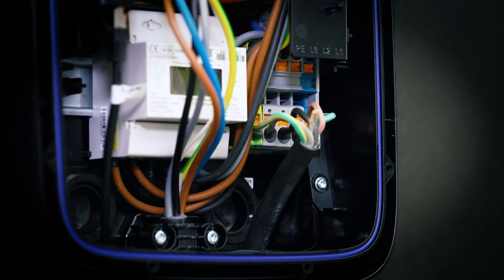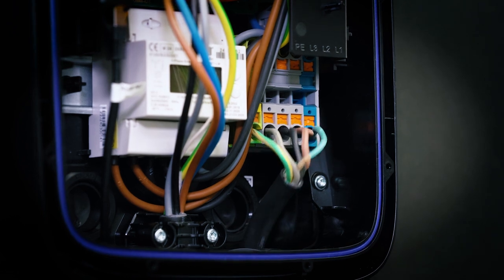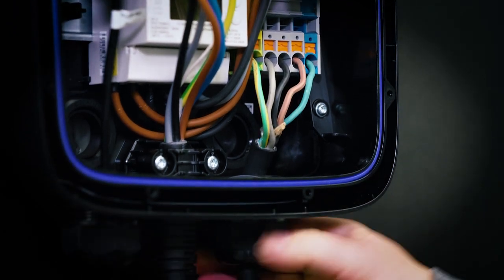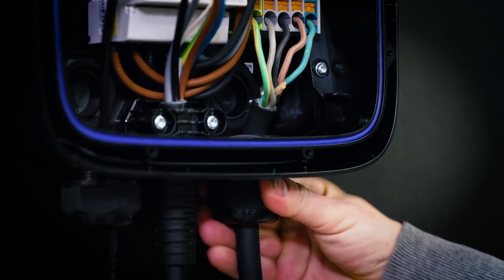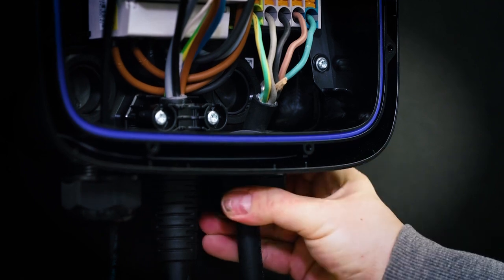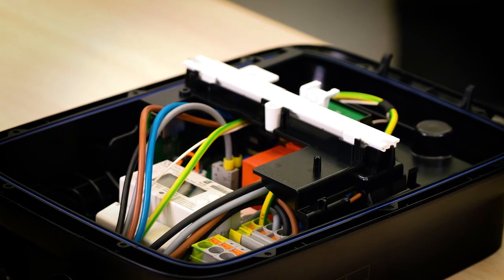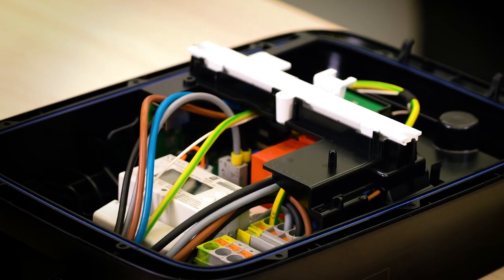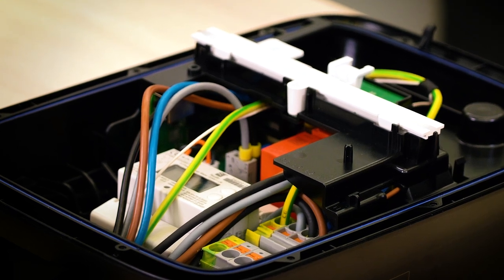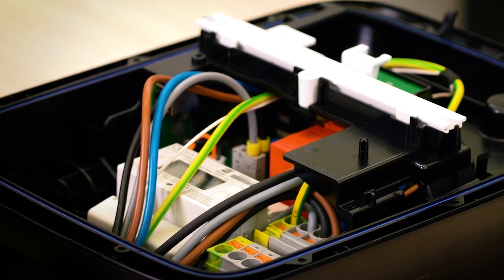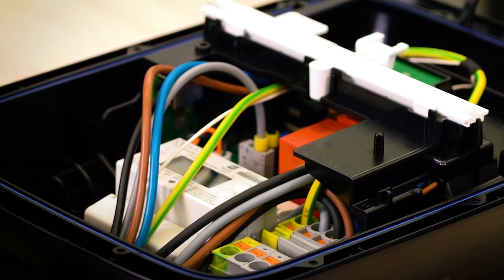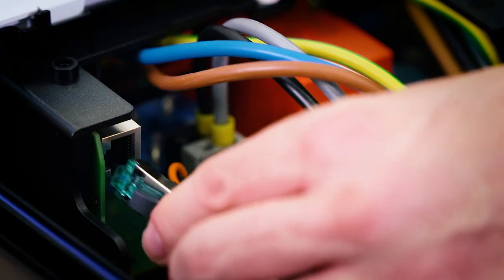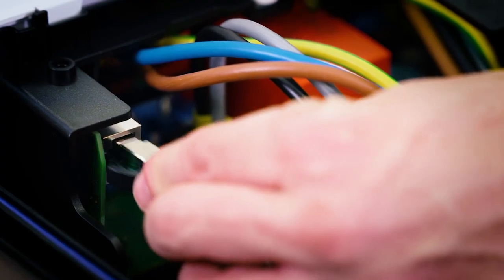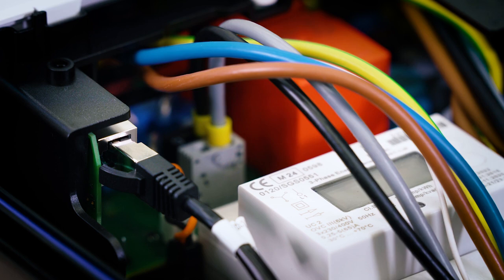Arrange the connectors as shown and insert them into the terminals. Tighten the cable gland sufficiently to ensure water and dust tightness and to prevent accidental disconnection. The Elli Charger 2 has a Wi-Fi interface, an RJ45 socket with eBus compatibility for Ethernet, and an RS485 interface for the Modbus standard. Use the RJ45 connector on the internal board to connect the Ethernet cable.